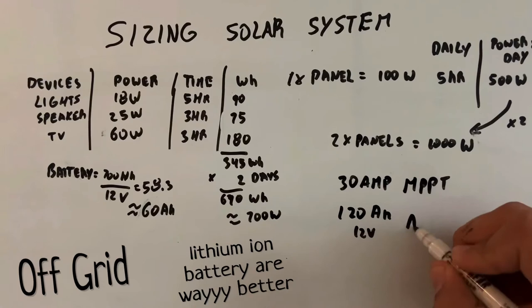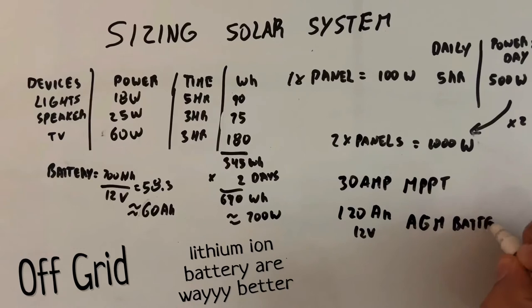Now remember that the AGM has a 50% discharge, depth of discharge. So for 60 amp hour requirements, we got to double that to 120 amp hours.